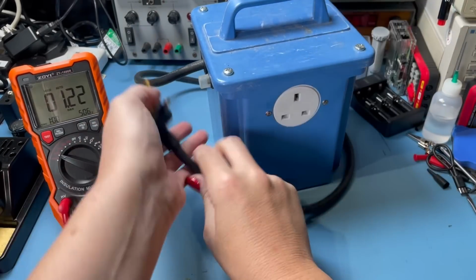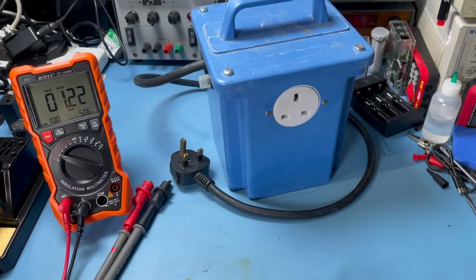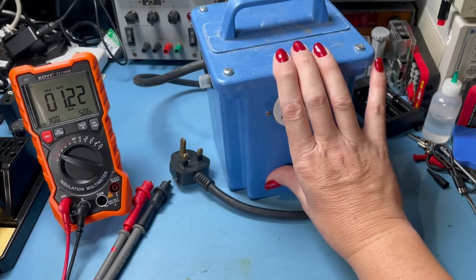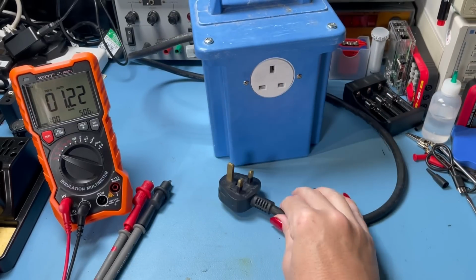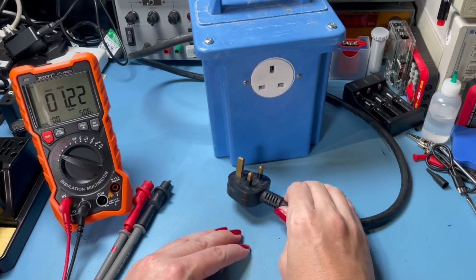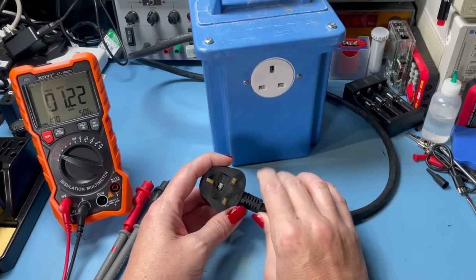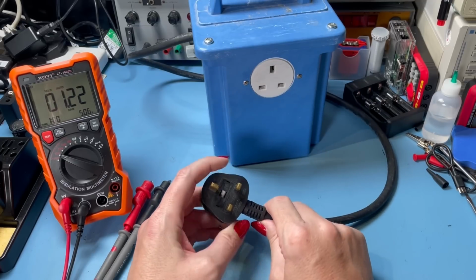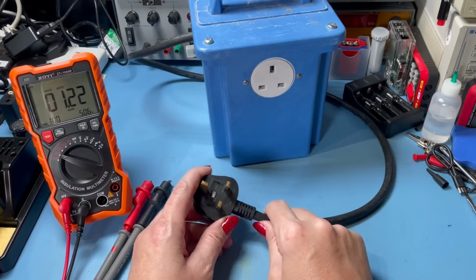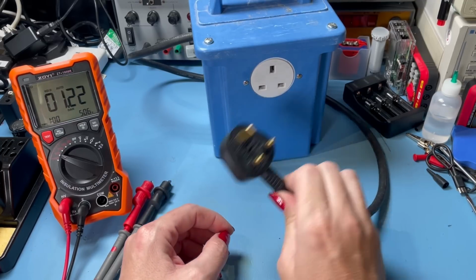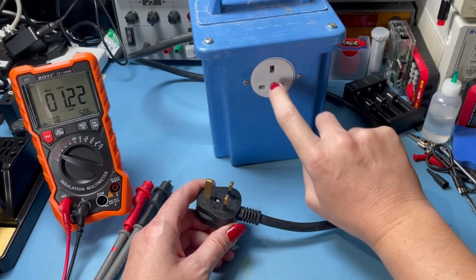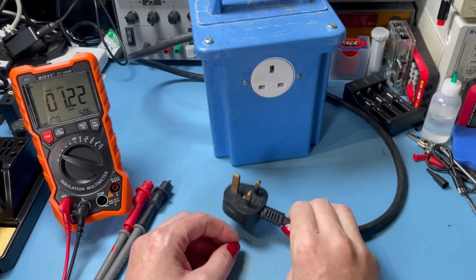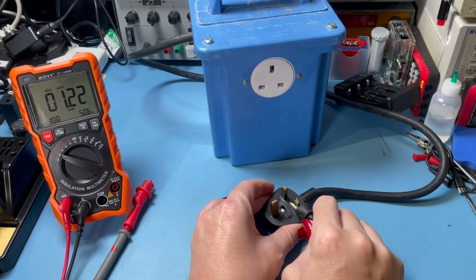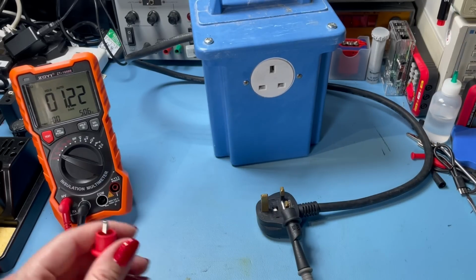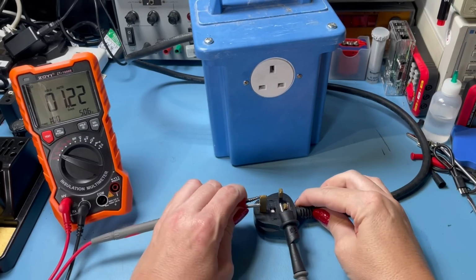Right, so if there's anything around here that's going to have good insulation, it's this. This is my good old isolation transformer. Now, we can certainly test this to 500 volts, and we're going to. And what I'm interested to see is not only what is the insulation resistance from the plug end of things, but I also want to see what I'm getting from here to here, because this should be isolated. This is a good way of testing this transformer. So let's do this end of things first. I'm going to speed through this so you don't have to sit through it all too much.